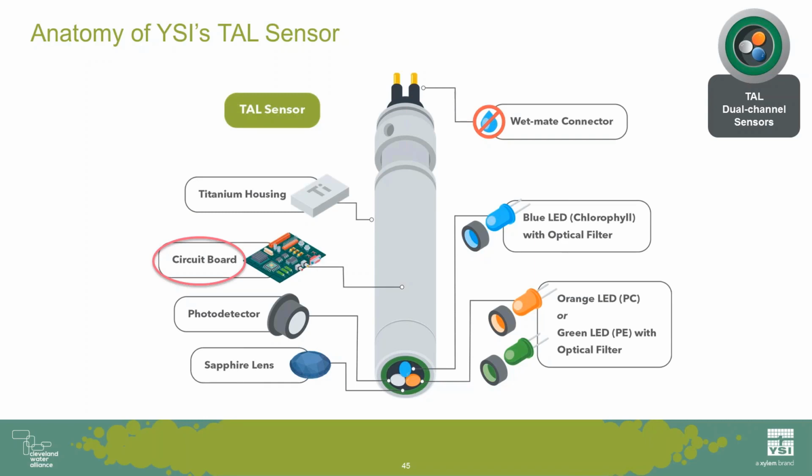Now, honestly, I'm a microbiologist, and when I started working at YSI 3 years ago, I did just have my 3-year anniversary, I came to learn that the circuitry in the sensor is sort of like a car engine in idle. It's always humming in the background and causing a baseline signal that we actually call the noise.